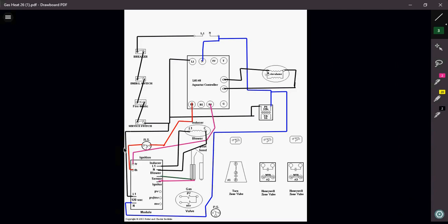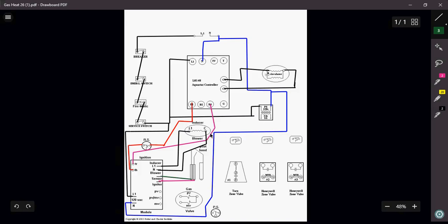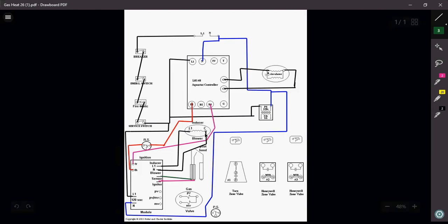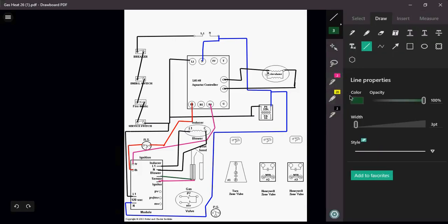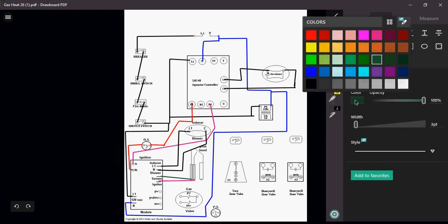I'm going to jump up to my TT, my 24 volts secondary, and all of this happy stuff that's going on over here. This is where it can kind of get a little hairy. Remember, our thermostats and our zone valves are getting powered with 24 volts. That 24 volts is coming from a second transformer in the system. It's not coming from the transformer that is in our aquastat. It's coming from somewhere else.